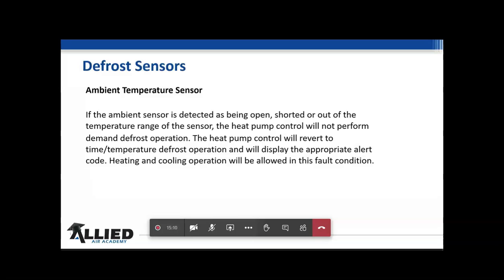And the reason I put this on here is if they get the codes on their phones and all that good stuff, and the homeowner calls and they look at it and they go, outdoor ambient sensor, well, if they know it's still going to work, they might bump that call to the last part of the day, knowing all I got to do is put on a set of sensors and go on about my business and take care of the ones who really don't have any heat and that type of thing. So that's what's going to happen. That's how this system is going to react if the ambient temperature sensor goes out.